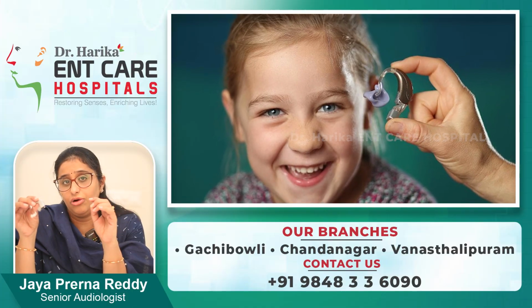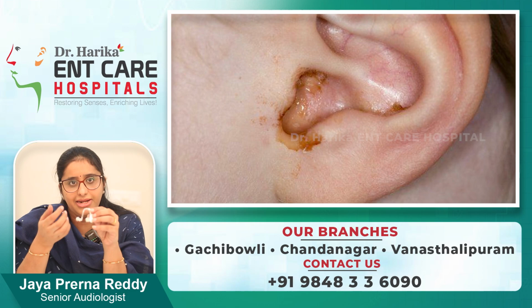If you see this hearing aid, this is the common hearing aid you must have seen around. RIC is a relatively new style of hearing aid. The BTE hearing aid has been there for a long time. This BTE hearing aid, a high power hearing aid, is given to children who have a lot of loss or to patients who have regular ear discharge, like I mentioned. This pipe is called a tube, which can be easily replaced and is very cheap.